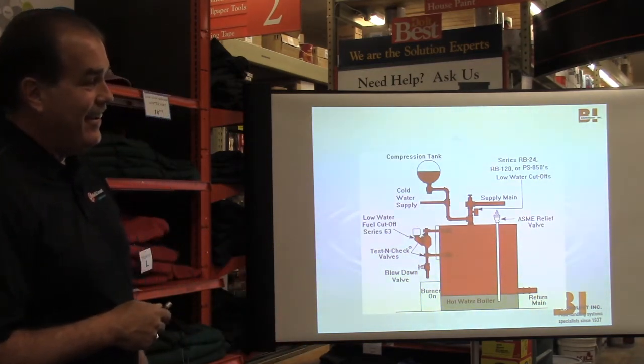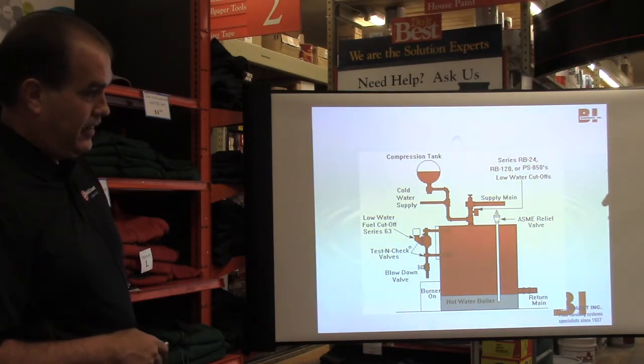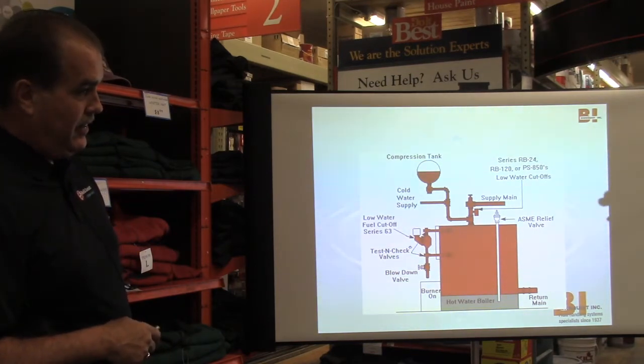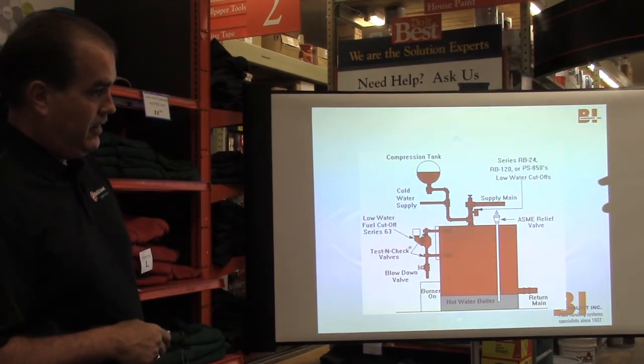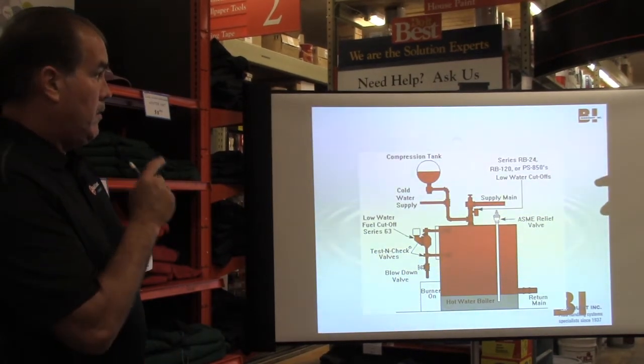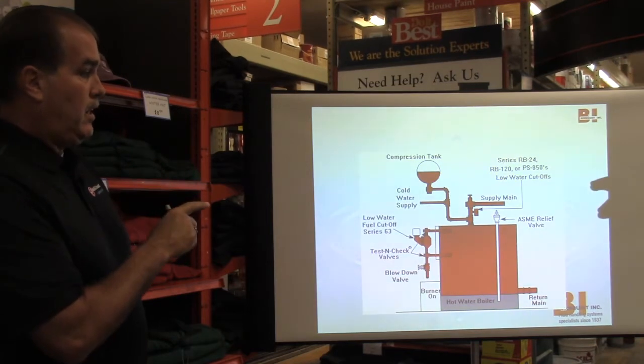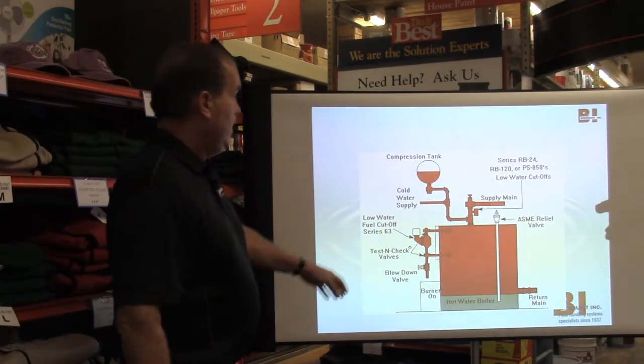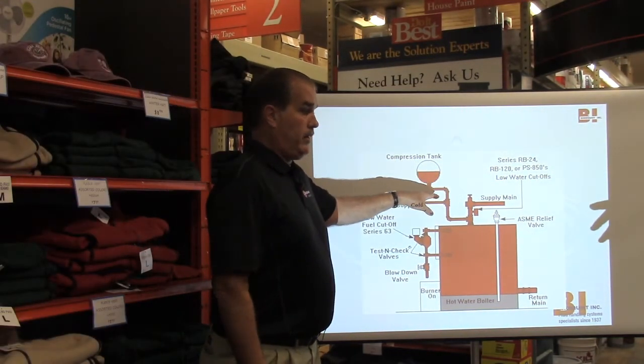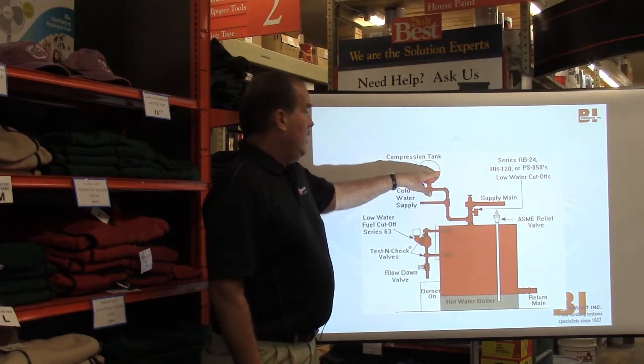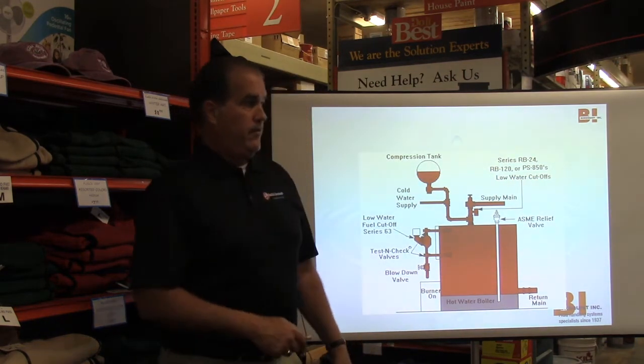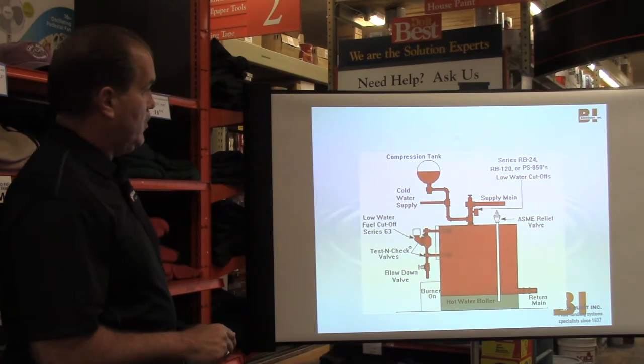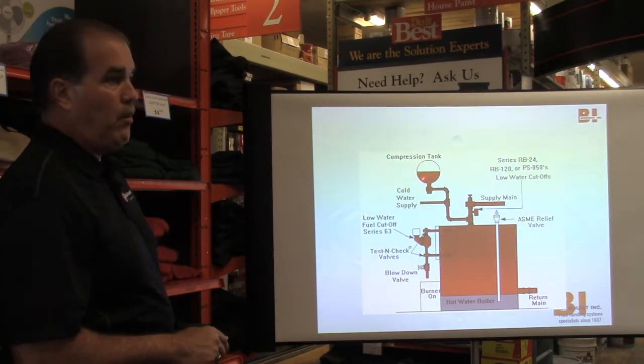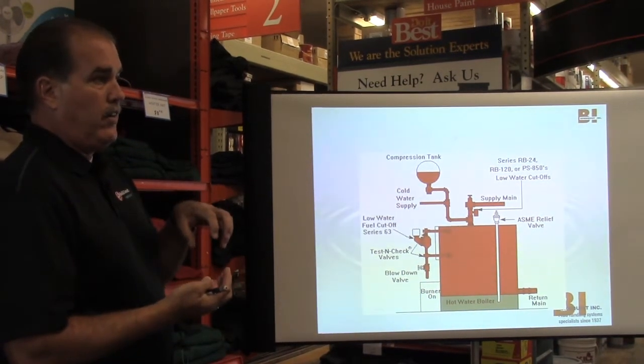Can I ask you a question? The compression tank, you just mentioned it has to be drained every year, right? There's a difference between a compression tank and a diaphragm tank. A compression tank, yes, you are 100% correct on that, because in a compression tank, there's no separation between the air and the water. The air and the water are touching each other.